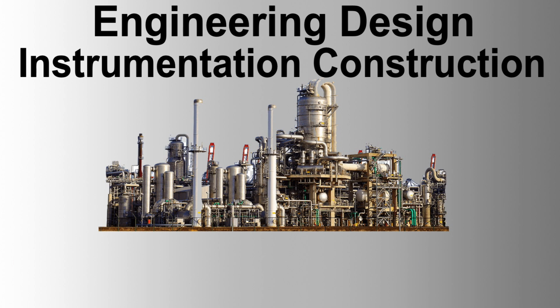Documentation. Detailed records of all cable terminations shall be maintained, including cable identification, termination locations, and test results. Documentation shall be kept up to date and submitted as part of the project handover package. Quality control. Terminations shall be inspected by qualified personnel to ensure compliance with project specifications and standards. Regular audits shall be conducted to verify that terminations are performed correctly and consistently throughout the project. By following these guidelines, the integrity and reliability of instrument cable terminations will be ensured, contributing to the overall performance and safety of the instrumentation system.